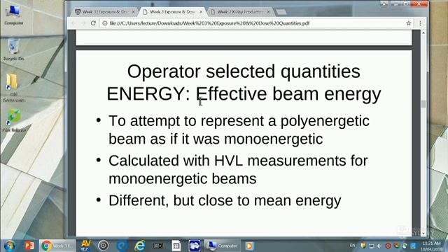Okay, so what you do is you go to your X-ray unit. So you wanted to compare, for example, your beam with this guy's beam, and you set the same thing, 70 and 30 mAs or whatever, okay? And you work out the half-value layer. So the half-value layer is the thickness of filter aluminium, for example, that will reduce the intensity by half, okay, for 70 and 30. This guy will do the same, okay? And your half-value layer might be 2.1, his might be 2.4.